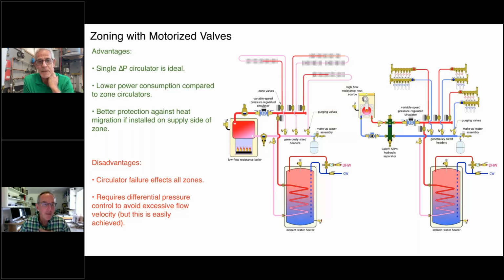of the loop. And so the momentum of the flow, the mass times the velocity, is the same on the supply and the return side. Yeah, and so is the differential pressure drop across the valve because you have the same flow rate, whether it's on the supply side or return side. So yeah, it's a hard thing to visualize for some people.